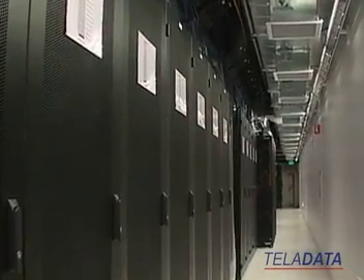And then we had our general contractor bring in a smoke producing machine, and sure enough, the smoke did show an airflow pattern of short cycling. So then we came back, installed all these curtains everywhere, and that seemed to solve 90% of the short cycling problem.